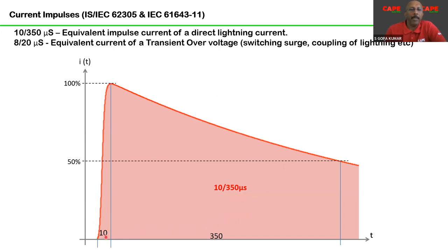microseconds. Means in 10 microseconds, the current probably, you know, 100 kiloampere, goes from zero to peak in 10 microseconds and it comes to half value in 350 microseconds. So basically 10 by 350 is an equivalent current wave shape of a lightning strike. Don't think that lightning always will be 10 by 350. It is not like that. This 10 by 350 is an equivalent representation of the energy contents of a lightning in the form of an impulse current.